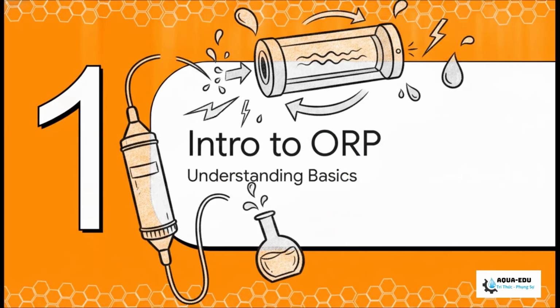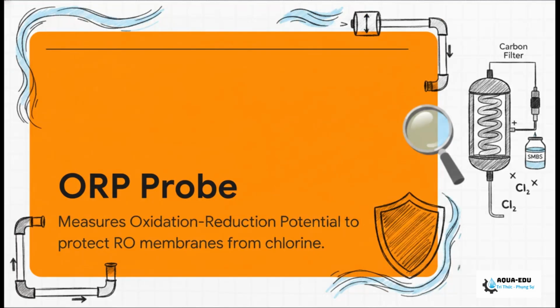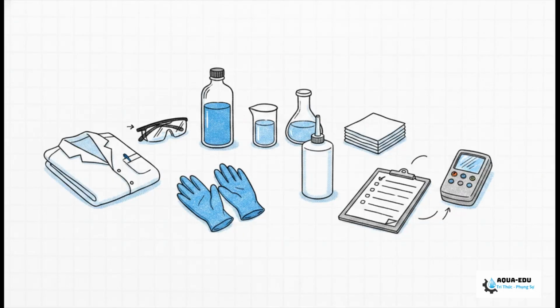All right, phase 1. Let's look at what these ORP probes are actually doing for us. As you know, we always position this probe right before the RO inlet. Usually that's directly after the carbon dechlorinator or right after the SMBS dosing point. Its one and only job is to guarantee our water has absolutely zero residual chlorine that could destroy that expensive polyamide membrane. It's measuring the oxidation reduction potential in millivolts. Basically, it's measuring the potential difference between a platinum sensing ring and, most commonly, a silver and silver chloride reference electrode. But before you even start, brothers, you've got to make sure your prep is perfect.